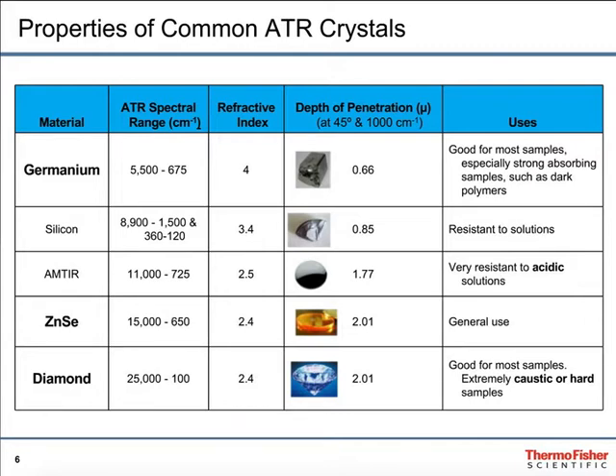The IR beam must pass through the crystal, and the crystal must be in contact with the sample. There are three parameters which define which crystals are used in a given circumstance. One is the spectral range — over what range does the crystal have a clear usable window? The next is the depth of penetration, which is how far into the sample the IR beam penetrates. And finally, there is the robustness — how the crystal material resists environmental wear. The most popular is diamond: it has a wide spectral range, a depth of penetration of about two microns, and it is the most robust of the materials.